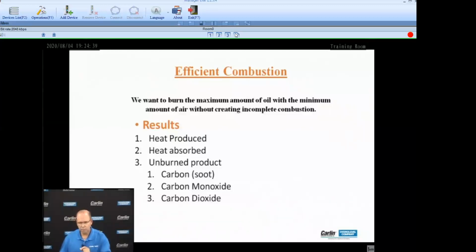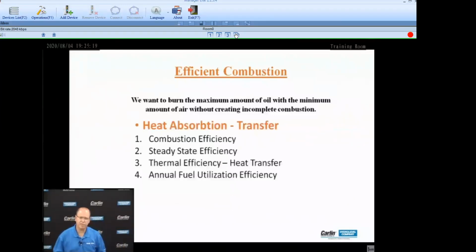Although there are no consequences from a very small amount of carbon monoxide, it's still there. It's not perfect combustion, and we all need to understand that. Where did the carbon dioxide come from? I'll take you back to the first slide. CO2, carbon and oxygen. One comes from the fuel, the other comes from the oxygen in the air. These are byproducts that are left over after the combustion process. So there was a chemical reaction here, and we started out with a few elements, and we end up with these compounds at the end of the process.